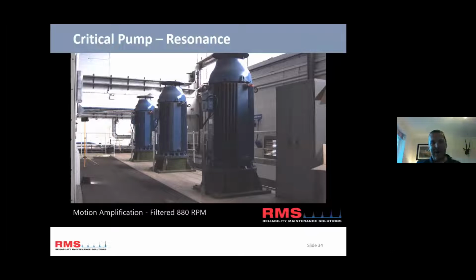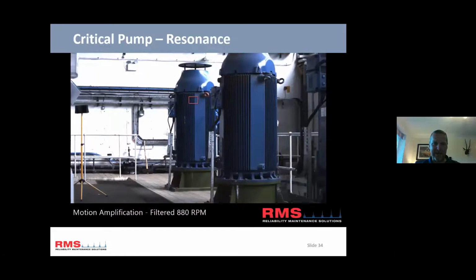This is one of my favorite motion amplification ones. It's a recent one from a water treatment works. They had 3 long reach vertical pumps, and one of them suffered quite badly from vibration at certain speeds. So again, resonance suspected. We did lots of tests, and then this is the motion amplified, and it's the pump at the far side. You can actually see the floor. This is on a suspended floor moving.